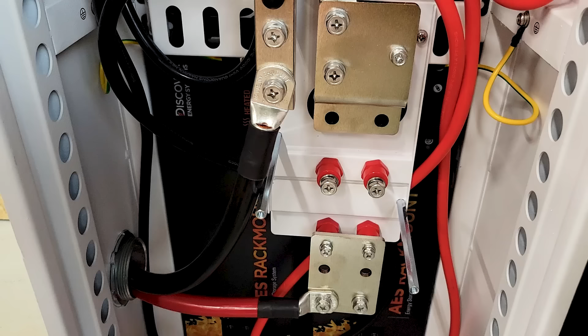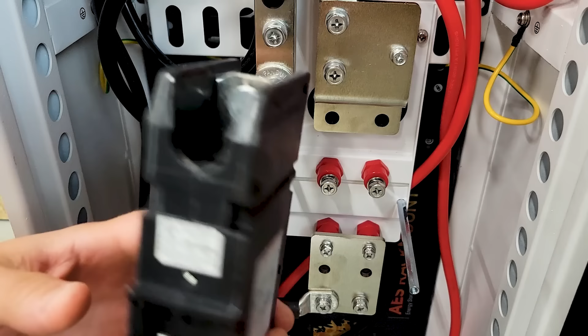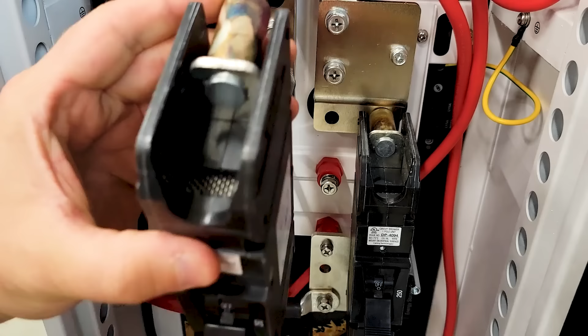Here's a close-up of the positive bus bars. Here's the positive coming down from the batteries, and there's the space for the circuit breaker with another positive bus bar. It looks like this one could be moved up and bolted here if you were not going to use a circuit breaker. But in the factory configuration, you can order a circuit breaker—one or two, because this battery cabinet is rated for 500 amps continuous, and this is a 250 amp circuit breaker. So if you wanted to run two, you could. I'm going to run one in my permanent setup, but I'll probably do some testing with both circuit breakers.